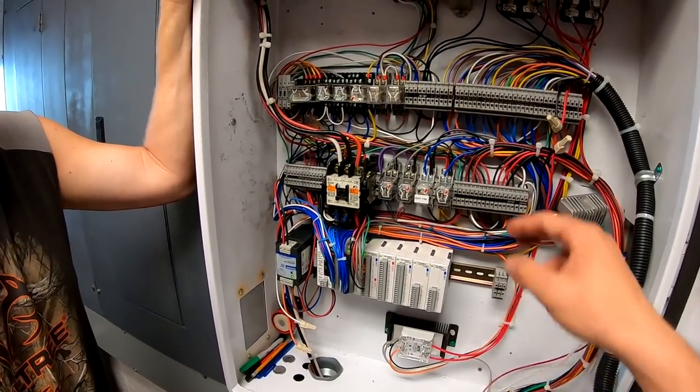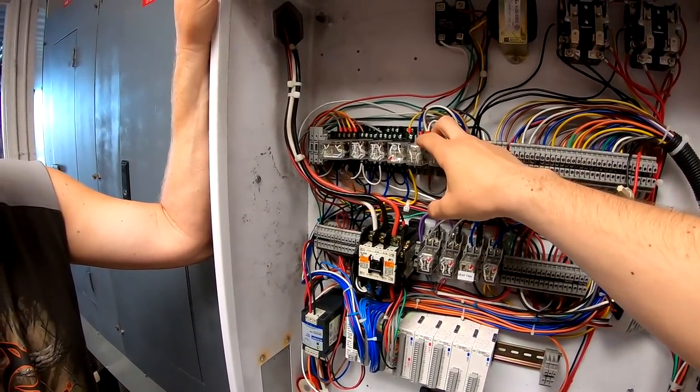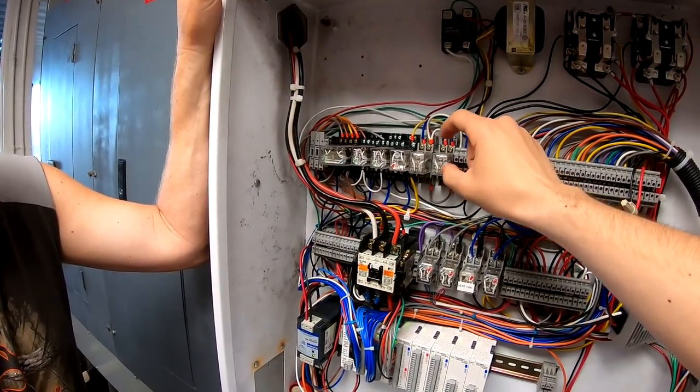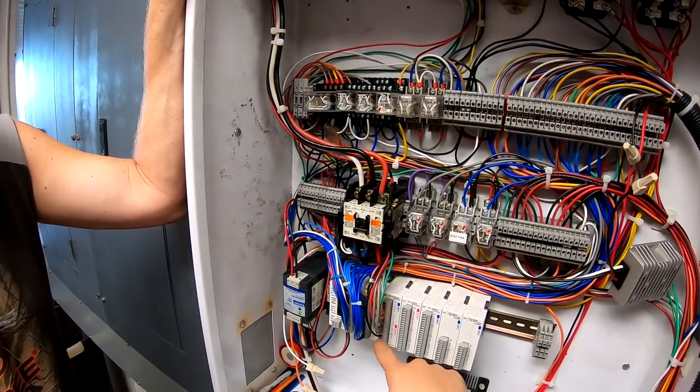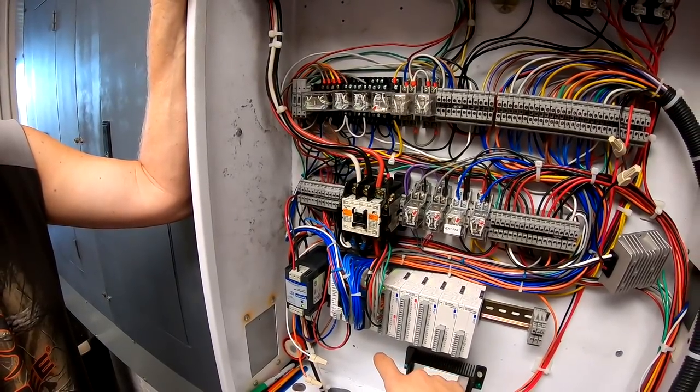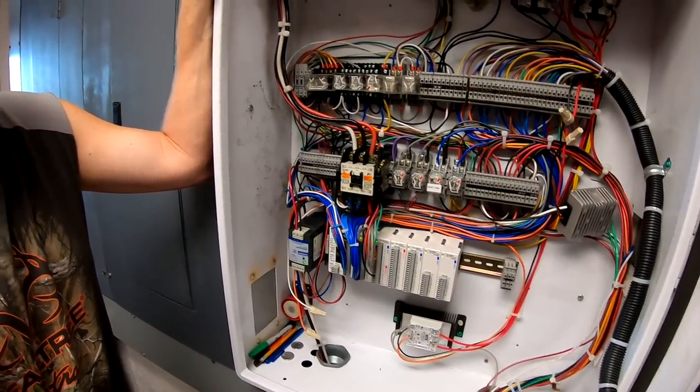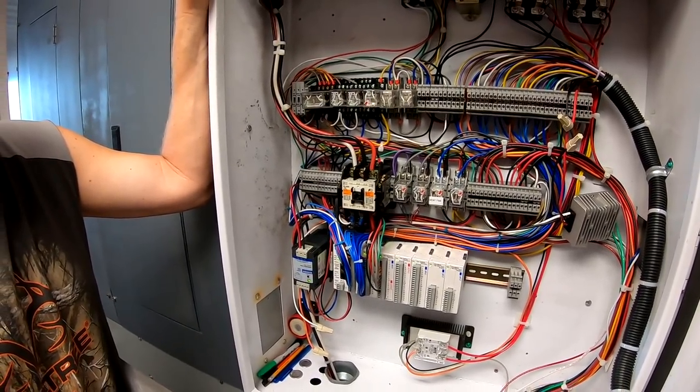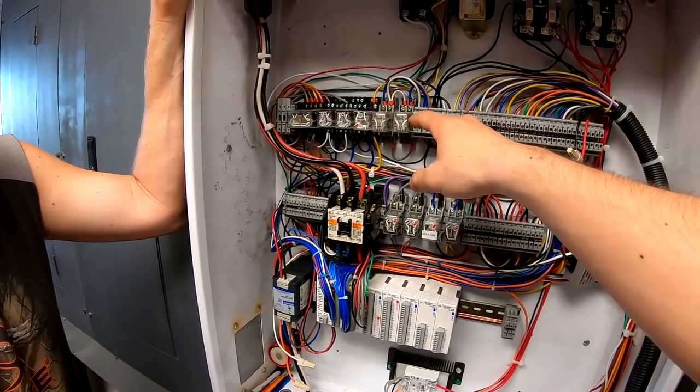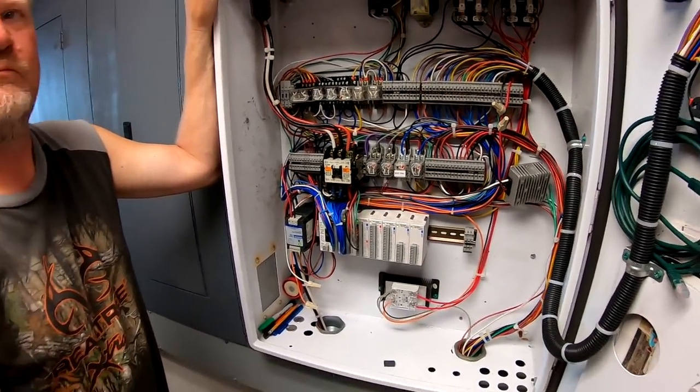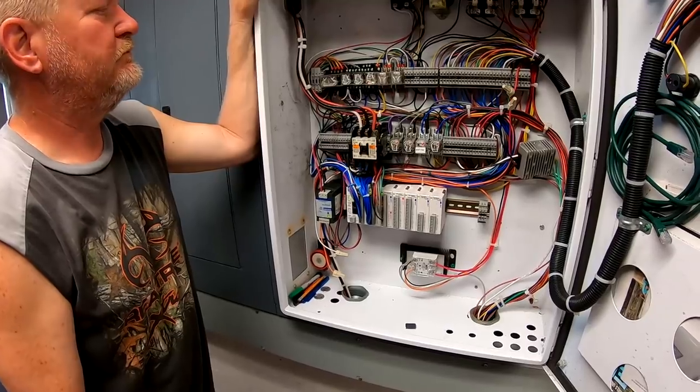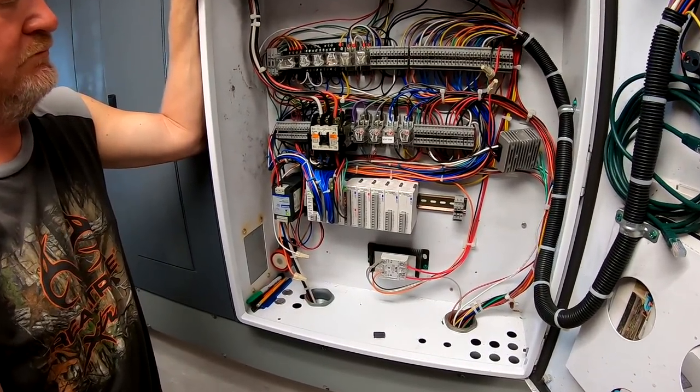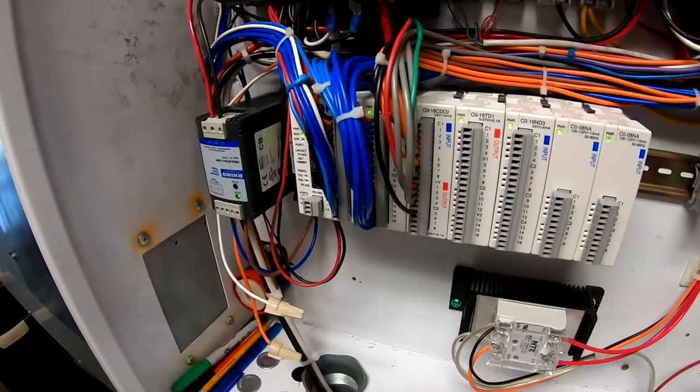So what I did here is I took the 240 volts off the back of the panel meter, and it's just closing a switch that runs 24 volts and then comes into here on a 24-volt input. But you lose a lot of sensing. So if we were to lose just one leg off that generator, only one of these relays would open and the PLC wouldn't know that you lost a leg and think the whole generator shut off. I see, that makes sense.